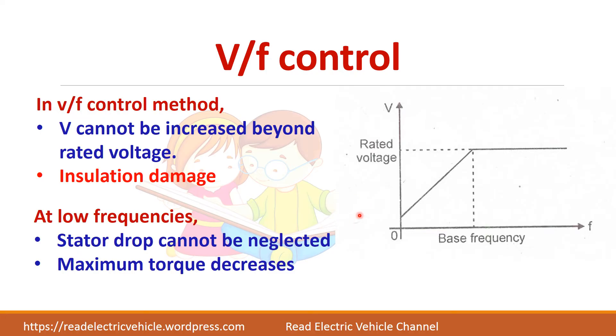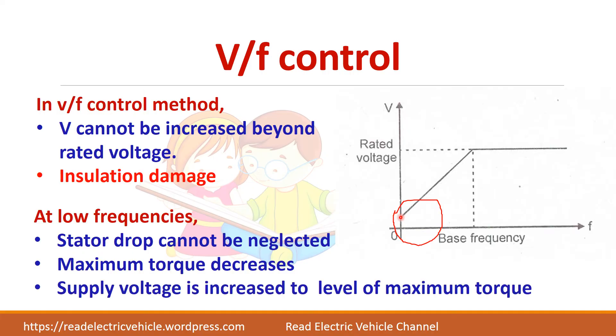At low frequencies, the stator drop which was neglected in deriving maximum torque cannot actually be neglected. So at low frequencies, maximum torque decreases. To compensate, a minimum voltage boost is applied — as seen on the graph, the V-F characteristic does not start from zero but has some initial voltage even when frequency is zero, ensuring sufficient torque at starting.